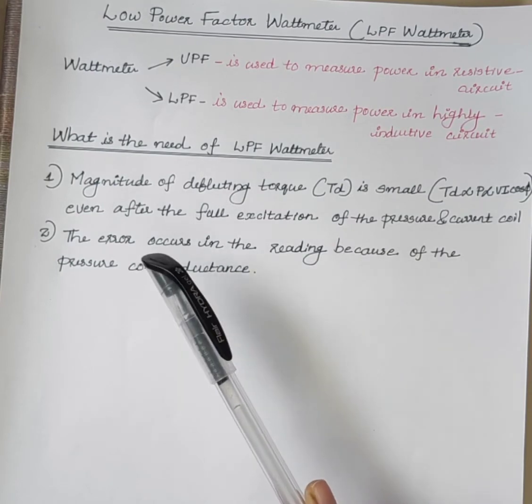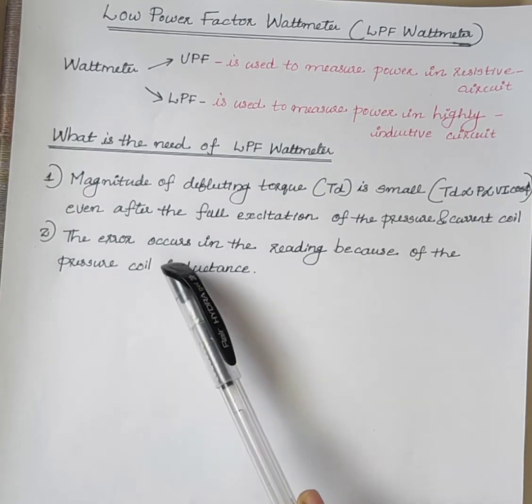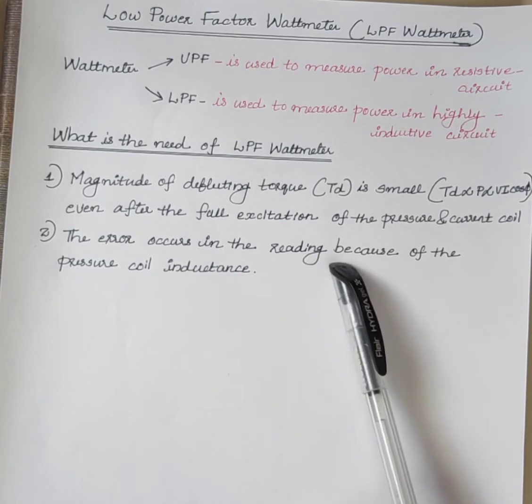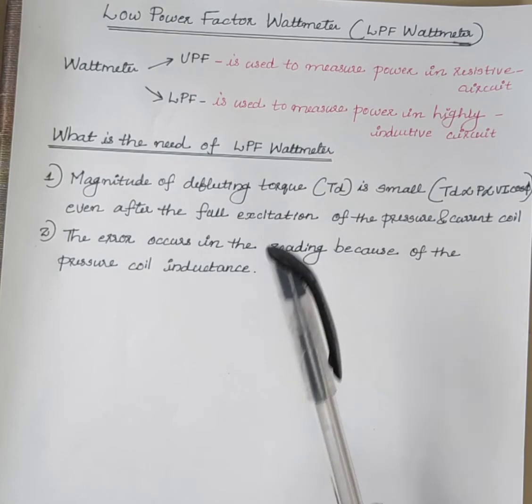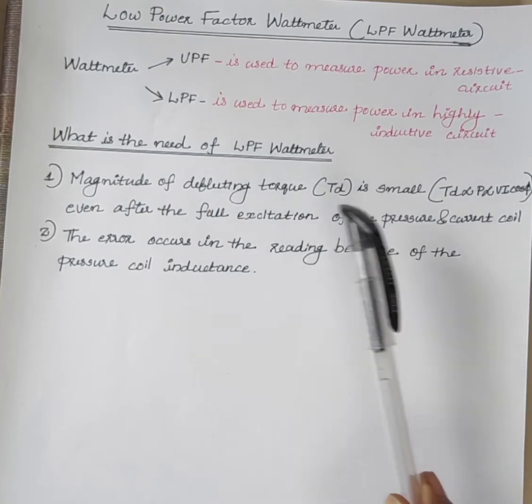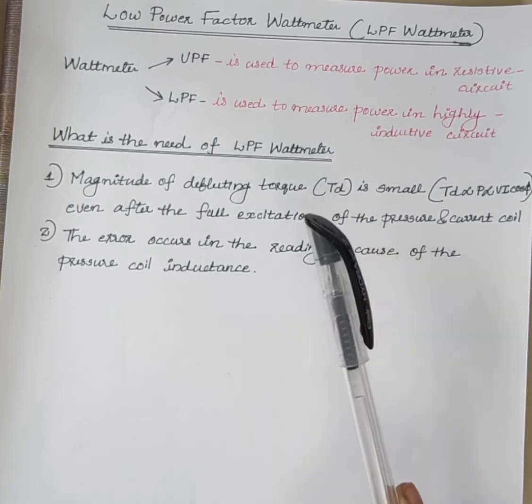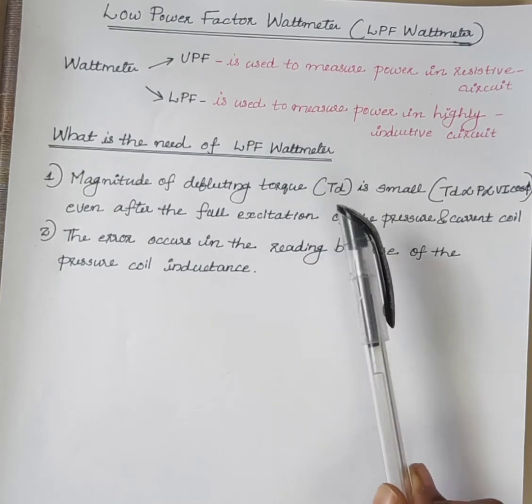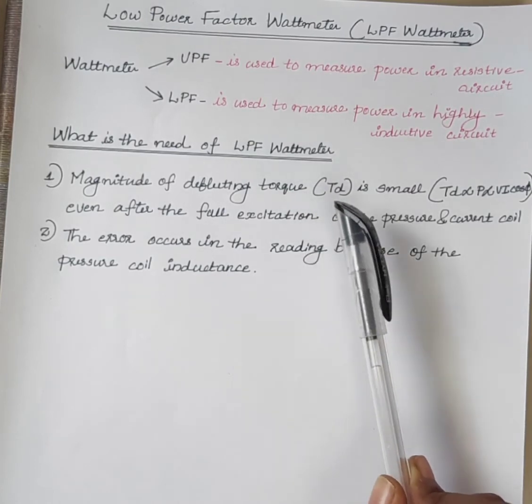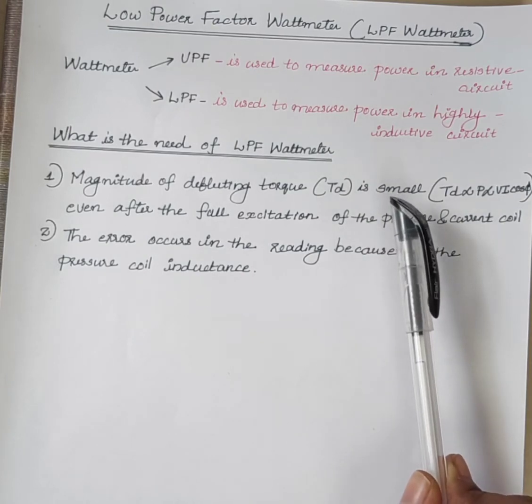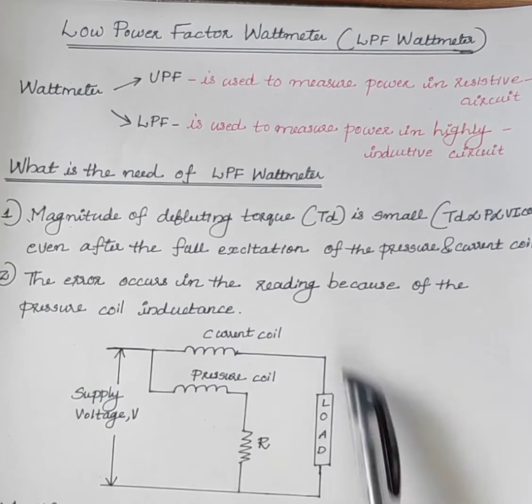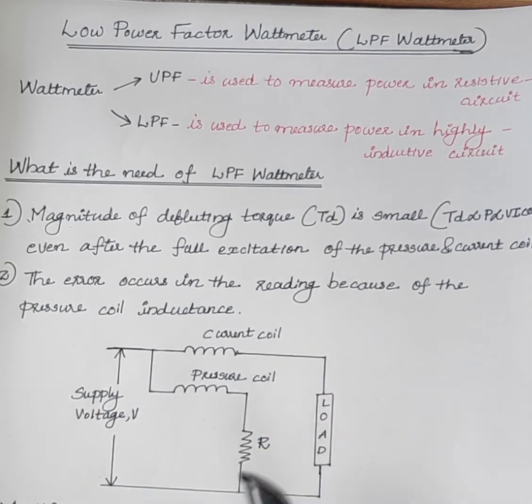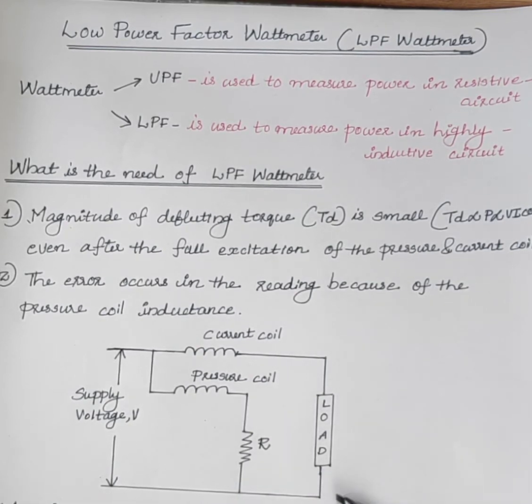The second reason is, if we are using an ordinary watt meter, error occurs in the reading because of the pressure coil inductance. So, some additional features are added to the ordinary watt meter so that the meter can measure the power of the low power factor circuit. Three major modifications have to be made in an ordinary watt meter to convert it into a low power factor watt meter.